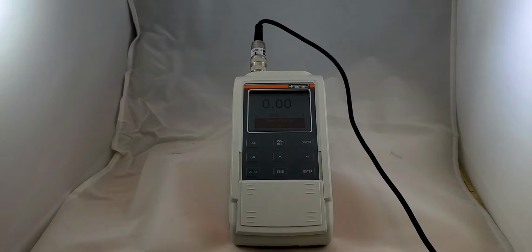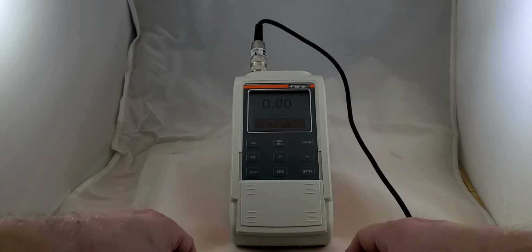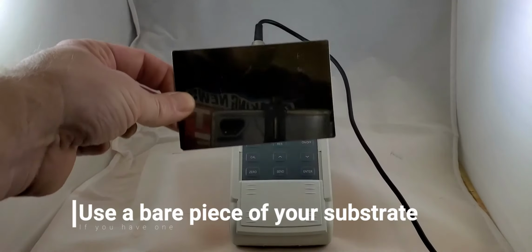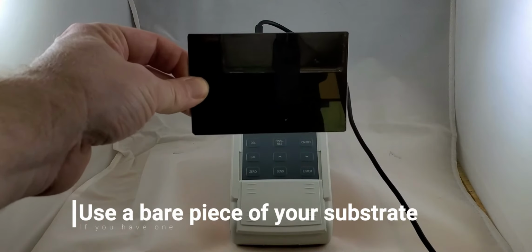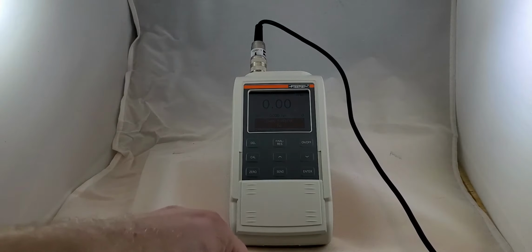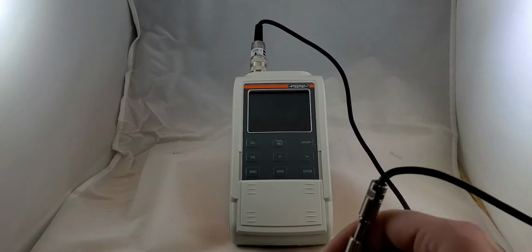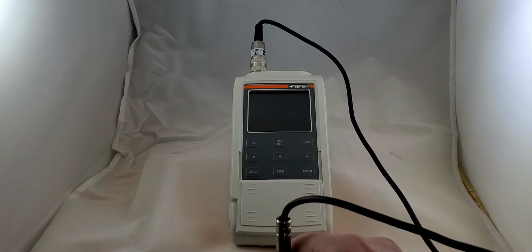Because this is a Deltascope, it's going to say that it wants steel. If it was an Isoscope, it would ask for a non-ferrous. If it was a Dualscope, it would give you the option, and you just toss in whatever substrate you want to calibrate for. If you have a bare piece of substrate, use that. If not, I have got a lovely piece of cold rolled steel, and we're going to use that as our substrate for the calibration. We're going to take 5 measurements.